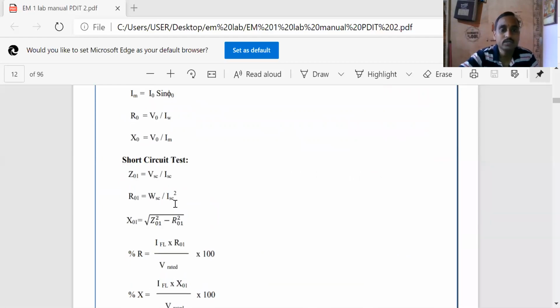For the short circuit test, Z01 and R01 can be calculated. Z01 is VSC divided by ISC, and R01 is equal to WSC divided by ISC square. From this, X01 can be calculated as the square root of Z01 square minus R01 square, as Z01 is known and R01 is calculated. This will give X01.